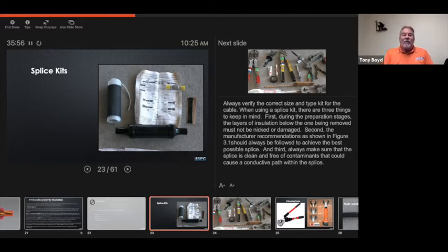So on the left-hand side, we have a cold shrink, which is a pull tape that will allow it to shrink down. This company uses that to seal the semiconductor shield and the concentric wires so that no moisture gets in and affects the cable. On the bottom is the splice kit. This is for the range around 175 mil type of insulation cable. And then at the top we have a 1/0. It's yellow, so it tells us that this is a 1/0 splice for the conductor.